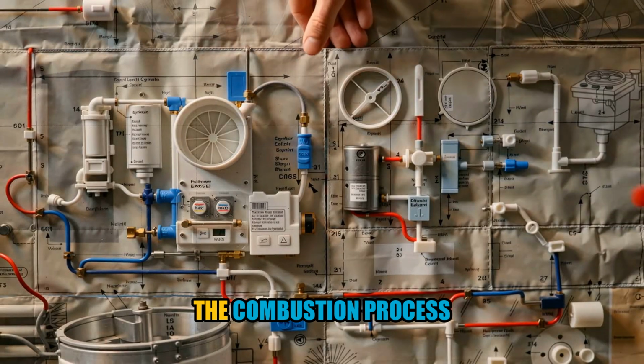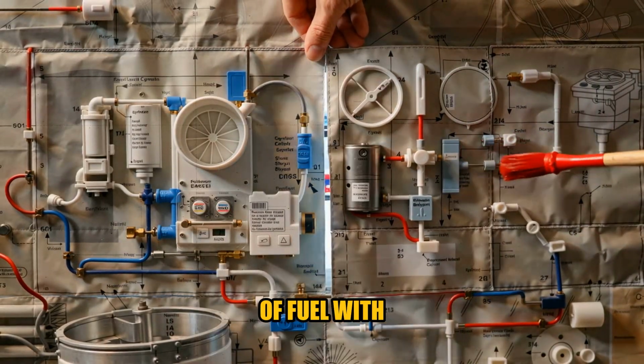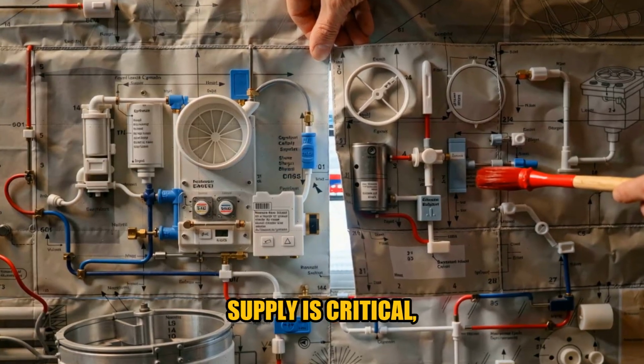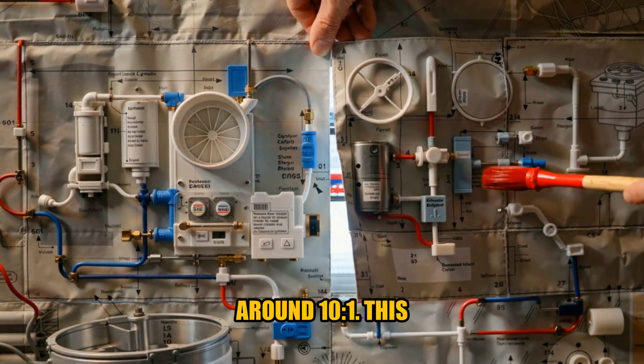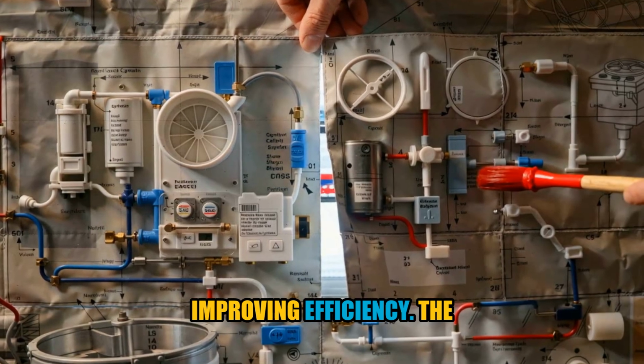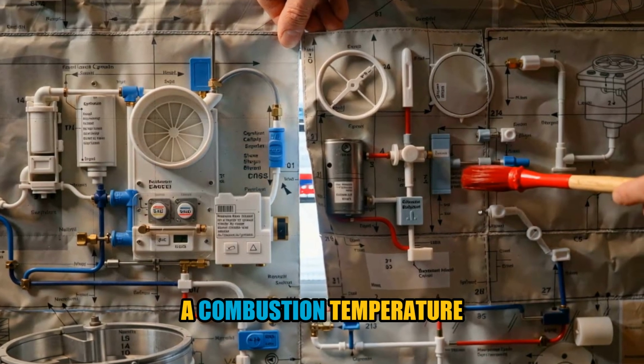The combustion process involves the reaction of fuel with oxygen, producing carbon dioxide and water vapor. The air supply is critical, with a typical air-to-fuel ratio of around 10 to 1. This ensures complete combustion, reducing emissions and improving efficiency. The burner's design enables a stable and efficient flame with a combustion temperature of up to 1800 C.